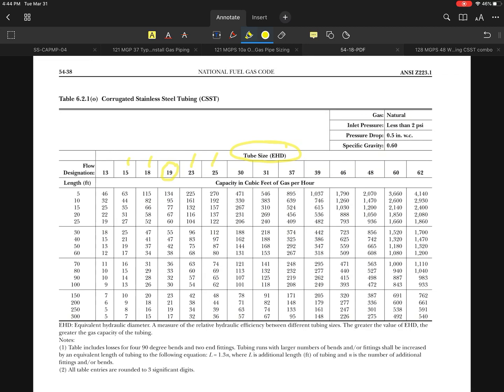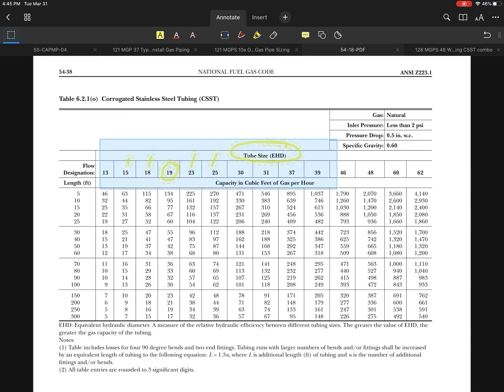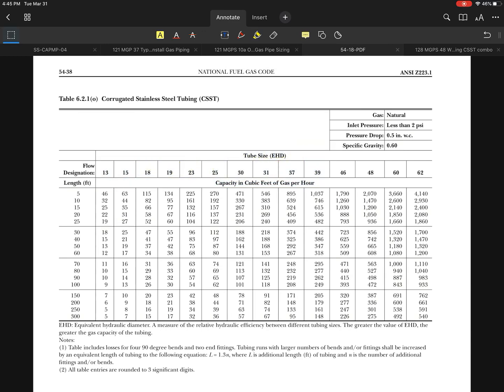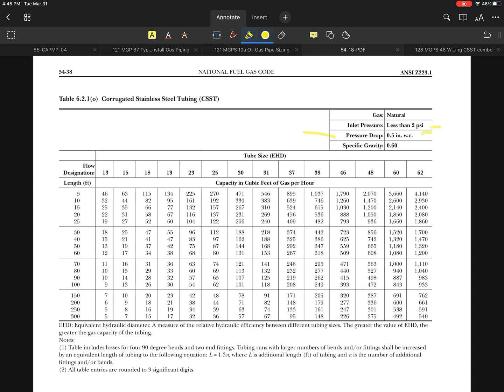You'll notice they also list a 15 and 18, they list 23, 25, and so on. Some of these are getting pretty close together. I'm assuming that's from several manufacturers that make just a slight variation on their tubing. Nothing major, but you want to be aware of it. You want to make sure you're looking at the right pressure. In this problem, I happen to have it set up where I'm using less than 2 psi. I've got a half inch pressure drop I can tolerate for this application.